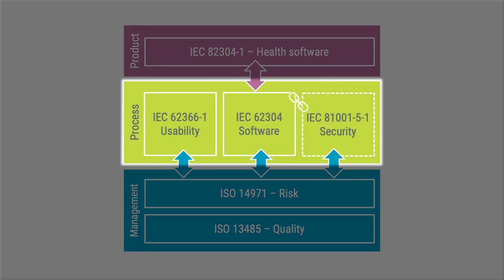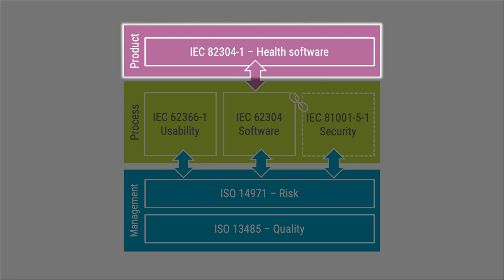The last process standard I want you to be aware of is IEC 81001-5-1, which is about security. It might not be applicable to all software products, but if you are working with standalone software, there is a high likelihood that security is something you should keep a close eye on. The next standard to cover in this overview is IEC 82304-1. It is a product standard for standalone software such as apps, PC programs, and cloud services that are supposed to run on generic hardware platforms. When working with standalone software, this standard applies to you and your product.